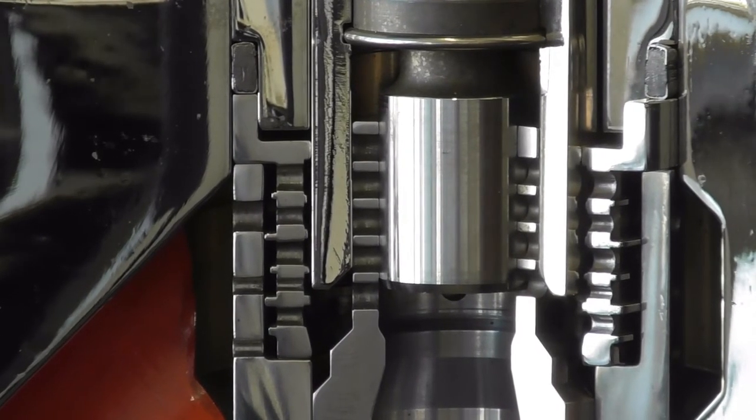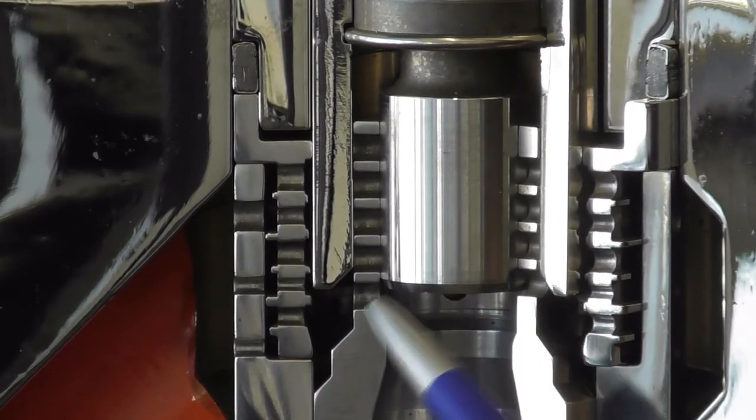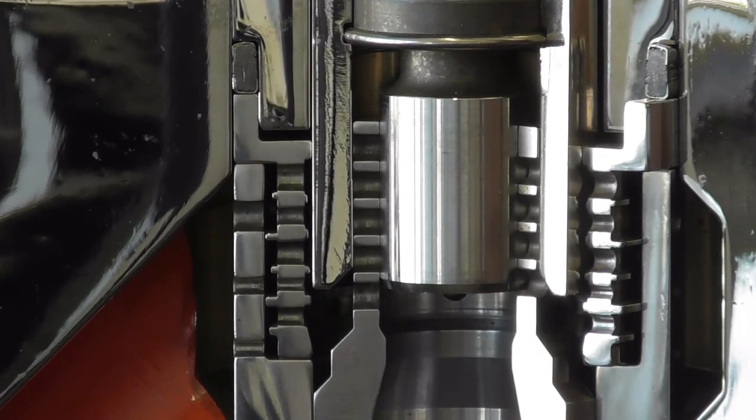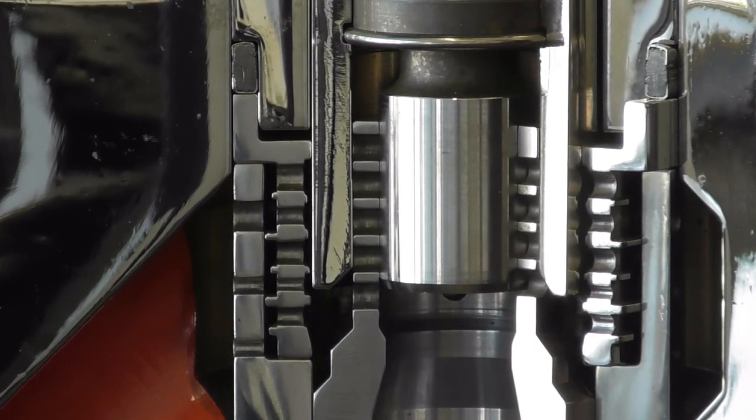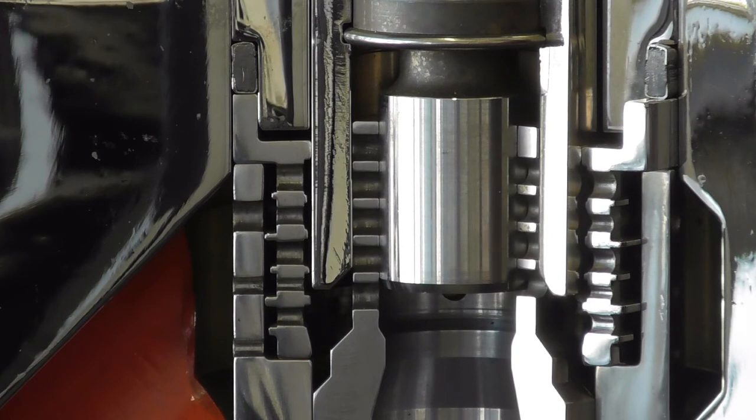This means that we have two seats, and this has the same function of a control valve plus an additional stop valve in one line.